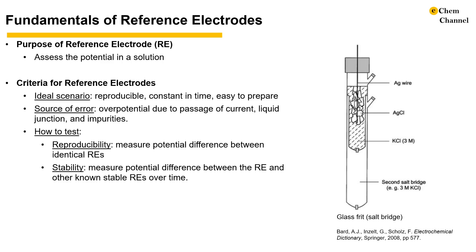To test whether a reference electrode is suitable for your electrochemical system, we can insert two reference electrodes of the same kind into your electrolyte, connect one as the reference electrode and the other as the working electrode. If the open-circuit potential is negligible — meaning the potential is in the microvolt range — the reference electrode is reproducible. Similarly, repeating the experiment with a reference electrode candidate and an established reference electrode and performing a long open-circuit potential measurement will tell us whether the candidate is stable over time.